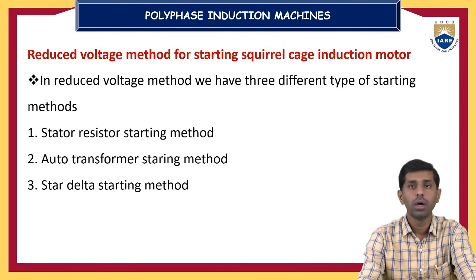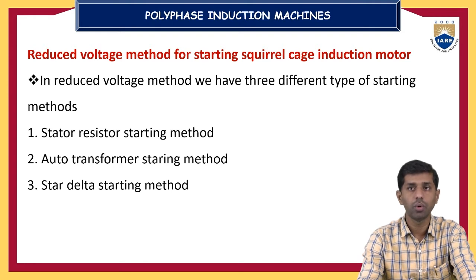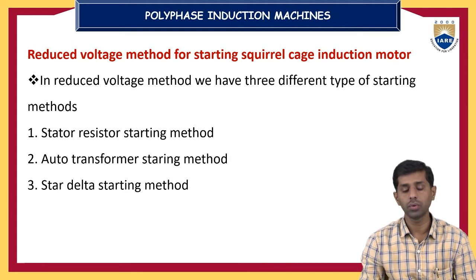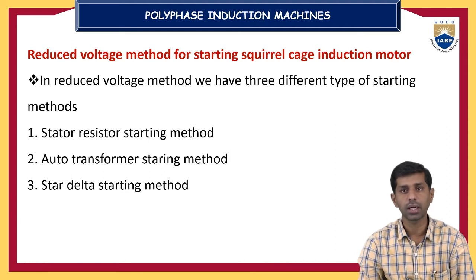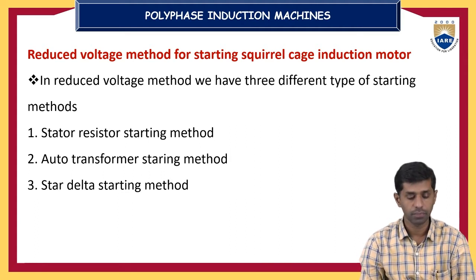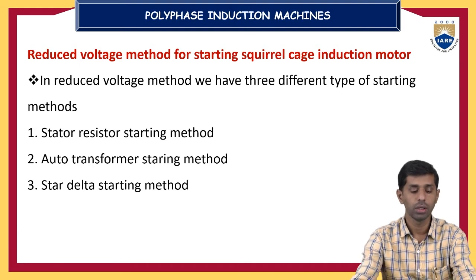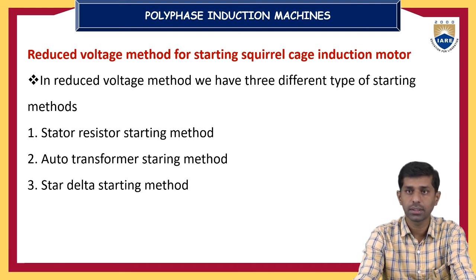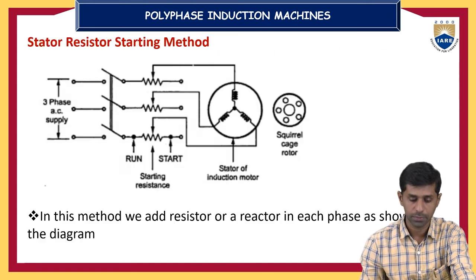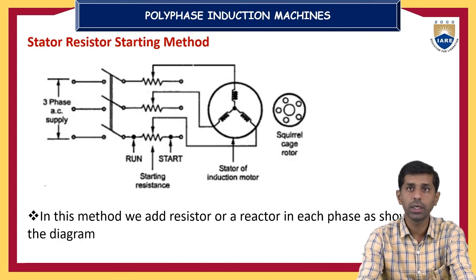So the next category is the reduced voltage method for starting a squirrel cage induction motor. In the reduced voltage method, we have three different types of starting methods: the stator resistor starting method, the auto transformer starting method, and the star delta starting method. First of all, we'll look into the stator resistor starting method.